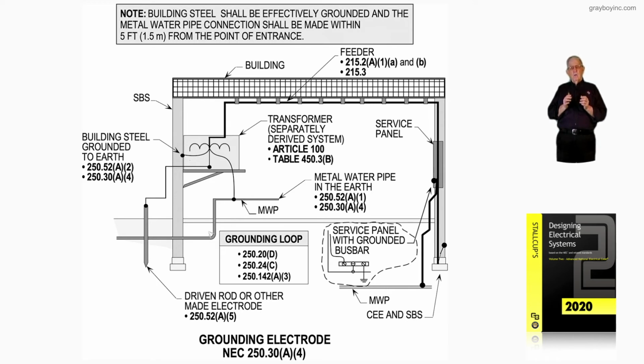But most all designers will design the conductors and the overcurrent device to that primary to allow the maximum kVA of that transformer to be used. So kind of keep that in mind. And then notice the note, it says building steel should be effectively grounded, and the metal water pipe connection should be made within 5 foot from the point of entry if it is an electrode with 10 feet or more of it in the earth as outlined in 250.52(A)(1), as in apple 1.